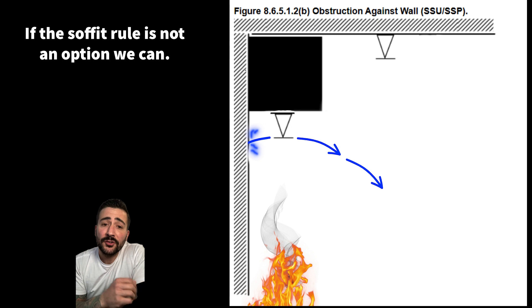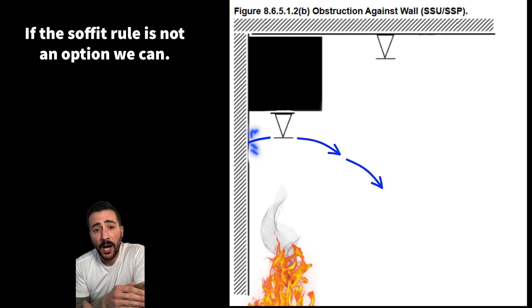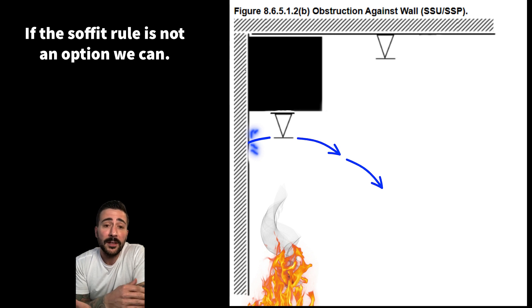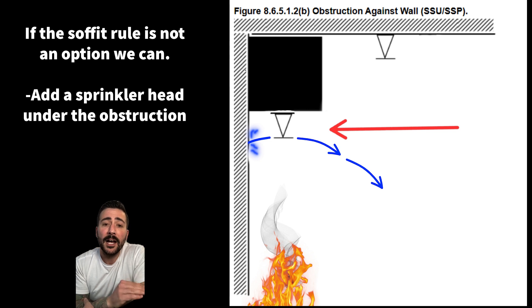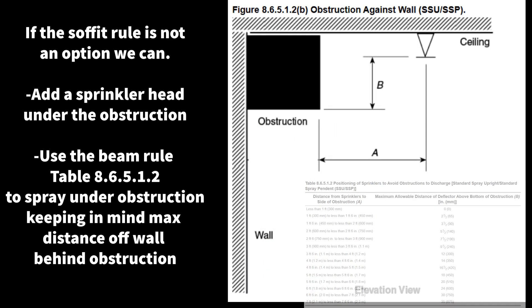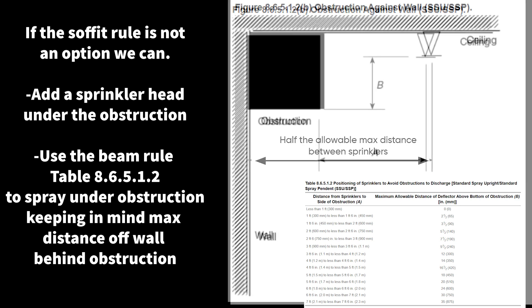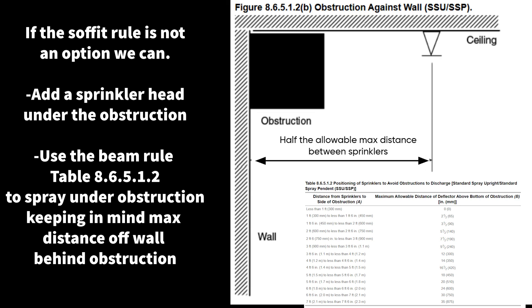If the Soffit Rule is not an option — maybe pushing the sprinkler head further off the side of the obstruction puts us too close to another sprinkler head, or maybe the obstruction is over 30 inches — in that case we put a head underneath the obstruction. Or you can always try to use the Beam Rule to spray under the obstruction, keeping in mind the max distance from the wall behind the obstruction to the center of the sprinkler head has to be half the max distance depending on the head you're using and the hazard occupancy you are in.